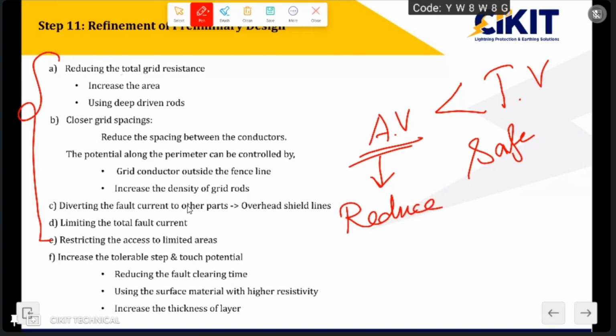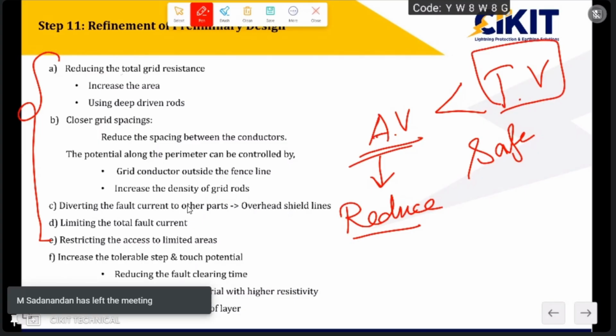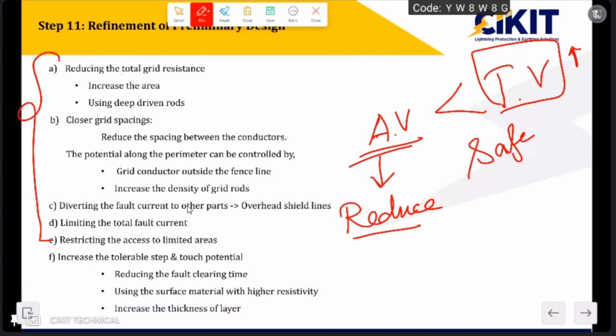But if there is no option available for reducing the actual value, then what I can do is increase the tolerable value. If I don't have any facilities for reducing the actual value, and I increase the tolerable value, then the criteria can be met. So the last point explains the provisions available for increasing the tolerable value so that I can achieve a safer design. The points provided by the standard for increasing the tolerable step and touch voltages include reducing the fault clearing time.